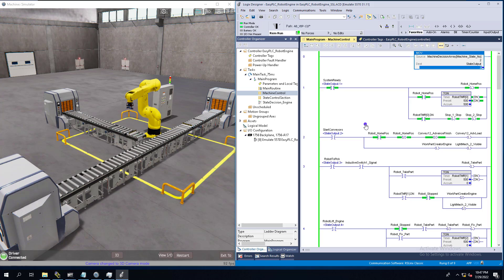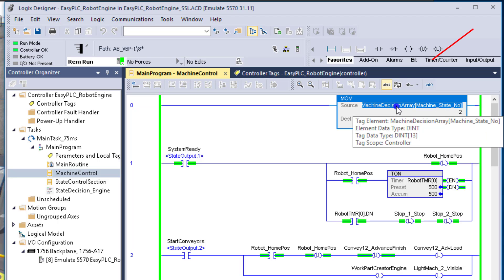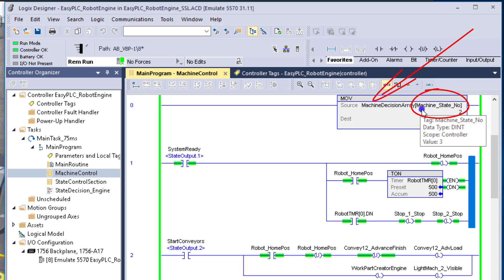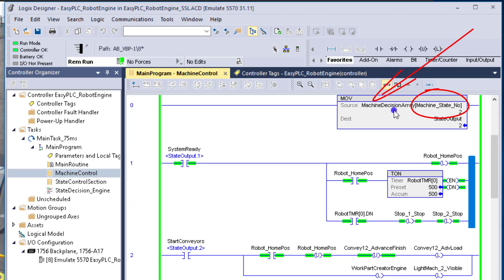In this video we're going to talk about a question I got asked about indirect addressing and how I was using it in a state machine. In this instance, this would be this move instruction right here — this indirect addressing called machine_state_number — and then that's going to load into an array. The number inside the brackets is going to point to that section in the array, which is a size of 13, but you can make it as big or as small as you want, as long as it accommodates how many states you're going to use.